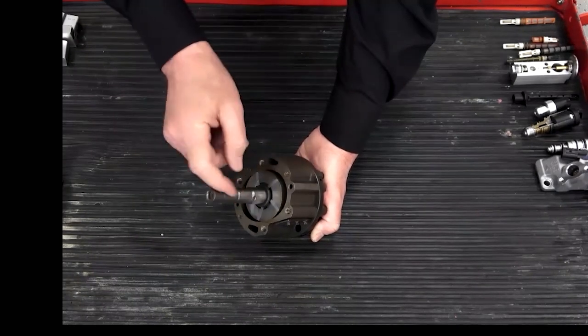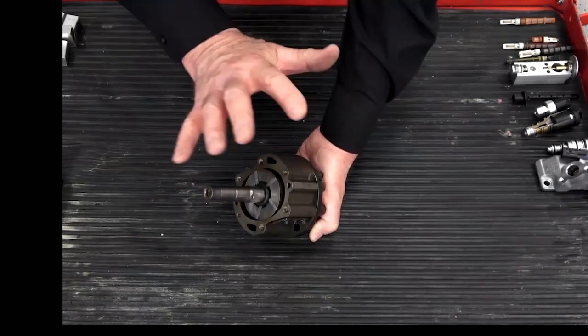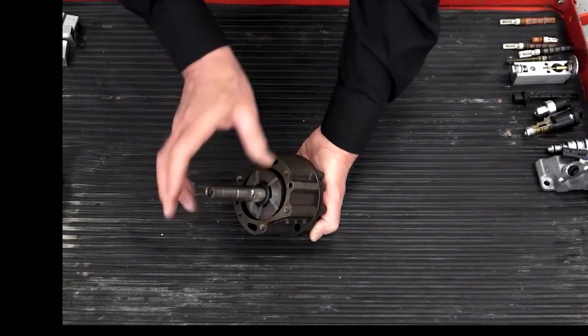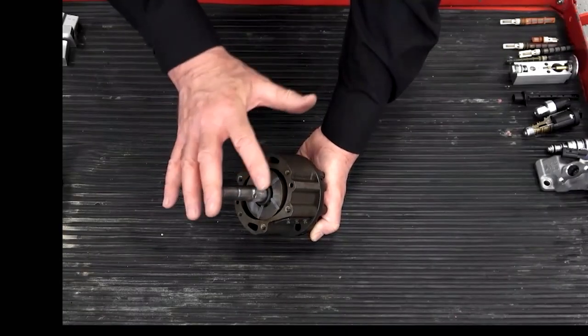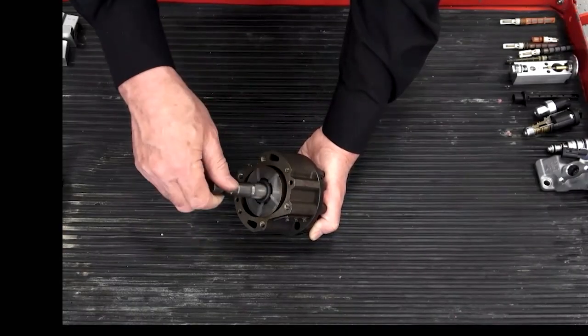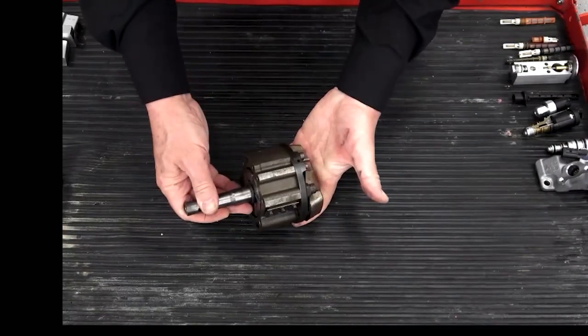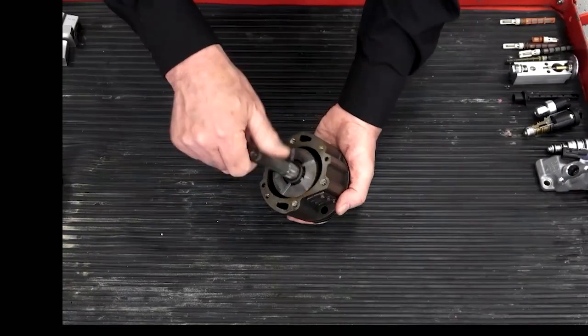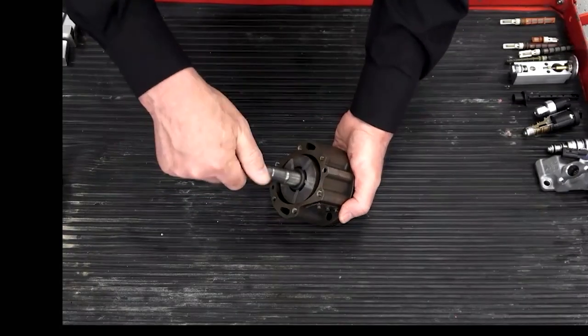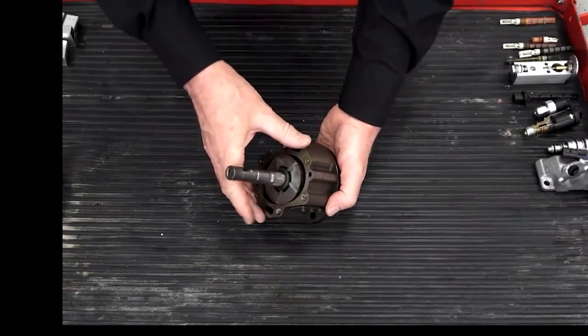These rotary vane compressors are particularly sensitive to oil viscosity. If you use too much oil, or the wrong viscosity of oil, the vanes can get stuck, and it can be really hard to get them to pump properly. So again, with a rotary vane compressor, turn it at 2,000 RPM, and oftentimes you'll be able to free up the vanes if they're stuck.